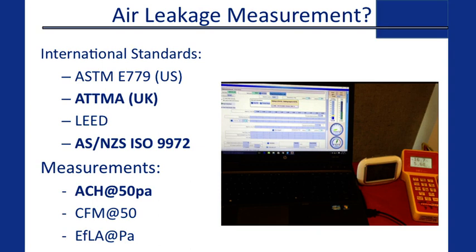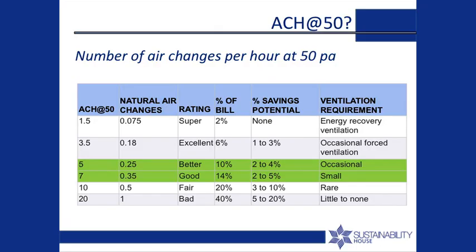So we've talked about where it leaks, how it leaks, how we find it — how do we measure it? There are a bunch of international standards, but the two main ones are ASTM and ISO, which we use in Australia currently. The most internationally recognised metric for residential housing is air changes per hour at 50 pascals — the number of times the air changes within the envelope at 50 pascals, which is roughly equivalent to a 30–35 km/h wind. The lower the number, the better — within reason for a naturally ventilated building.